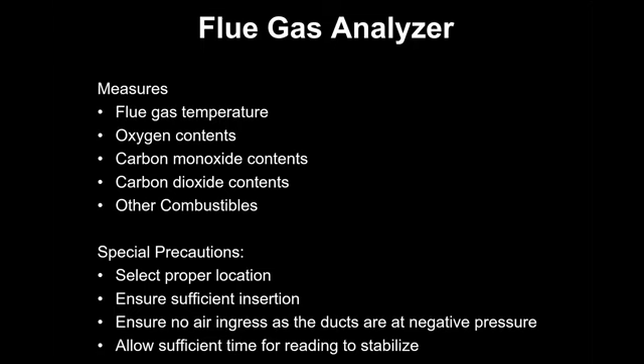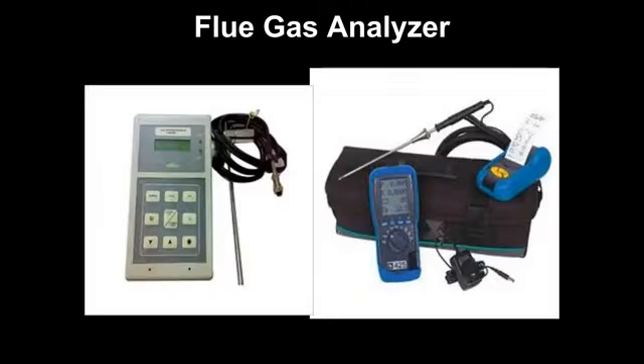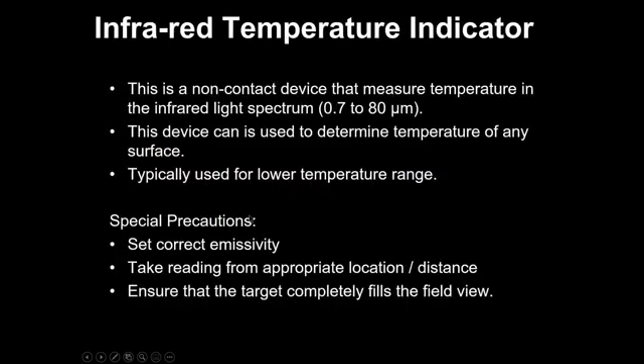Select the location properly, as I said, because earlier also I was saying that this becomes a very critical thing. Insertion should be sufficient. I explained in the beginning that if it is not sufficient, the reading could not be correct. Also consider air ingress and sufficient time to stabilize. These are the flue gas analyzers. These are all with smaller probes. What we have is almost 700 mm and 1 meter.